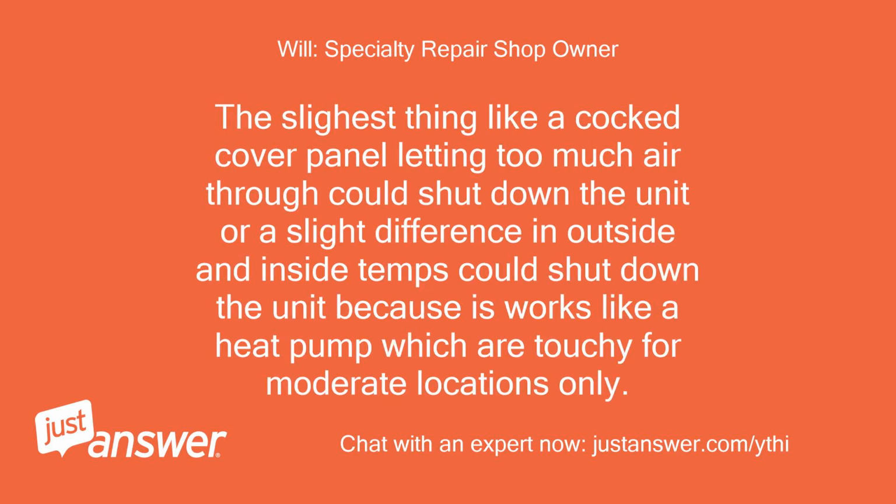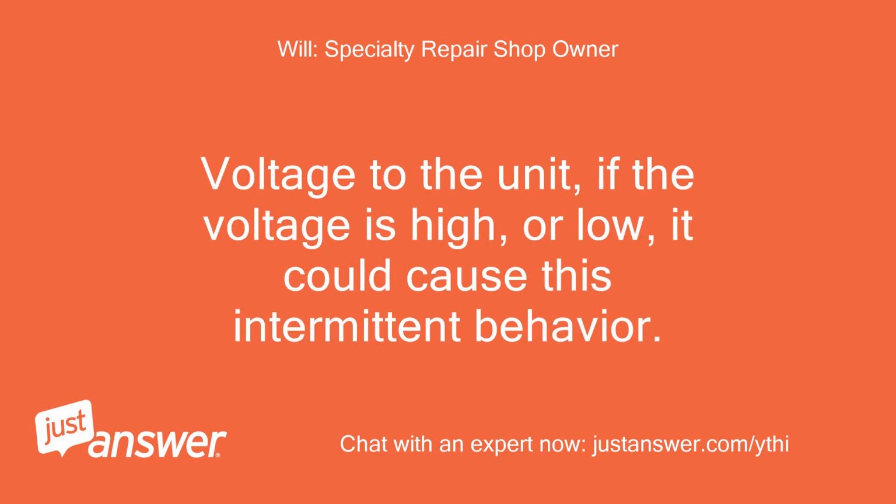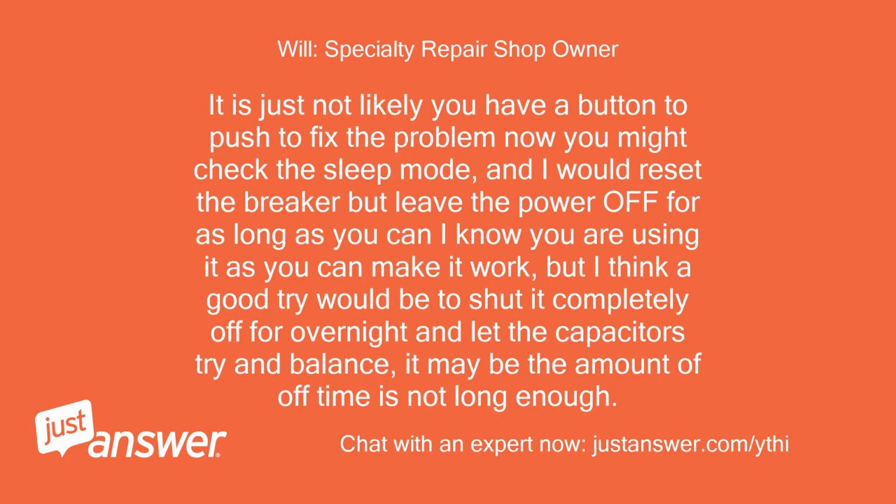The slightest thing, like a cocked cover panel letting too much air through, could shut down the unit, or a slight difference in outside and inside temps could shut down the unit, because it works like a heat pump, which are touchy and suited to moderate locations only. Check the voltage to the unit. If the voltage is high or low, it could cause this intermittent behavior. It is just not likely you have a button to push to fix the problem now.